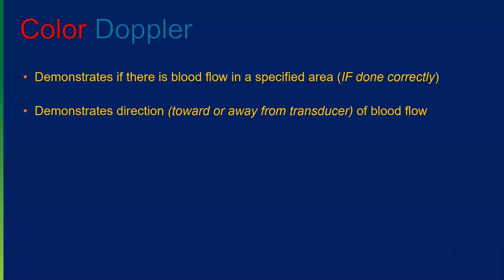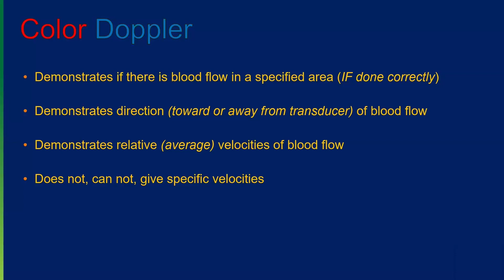Color Doppler also demonstrates relative or average velocities of blood flow. Again, using just the color, I can't determine how fast the blood flow is moving. I could very likely, and I'll show you examples of this, show you where the fastest flow is occurring, but then I'll need to come back with the pulsed Doppler to see what that actual velocity might be. It cannot give specific velocities. I can tell you where the fastest flow is occurring by what I see with the color Doppler display, but I cannot tell you actually how fast that might be moving, which is important when we get into diagnosis of things.